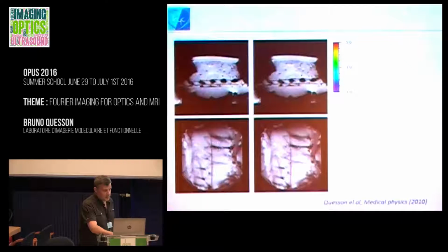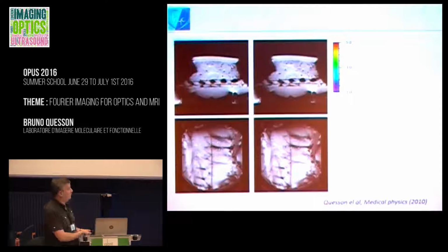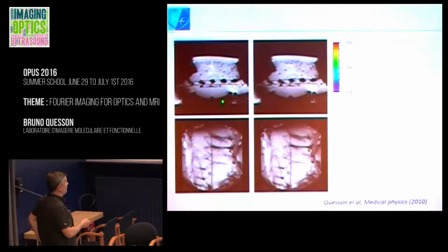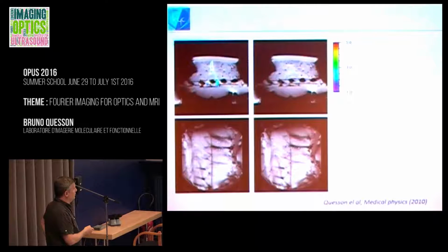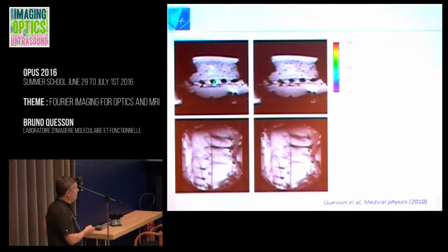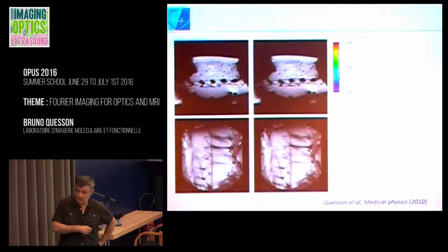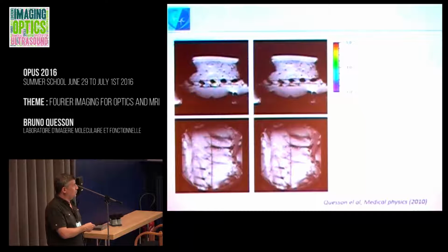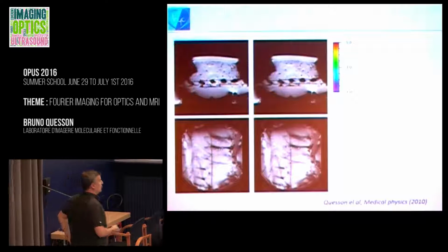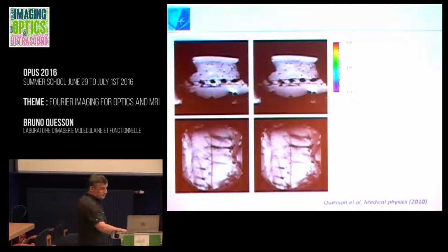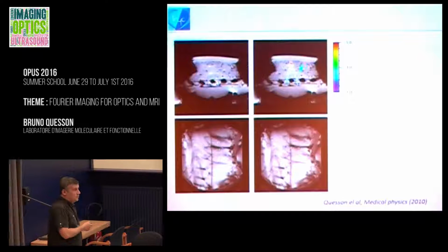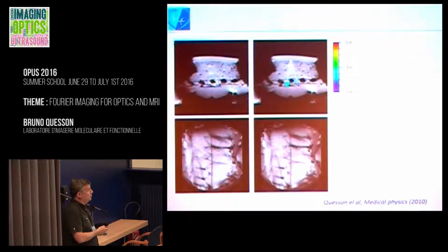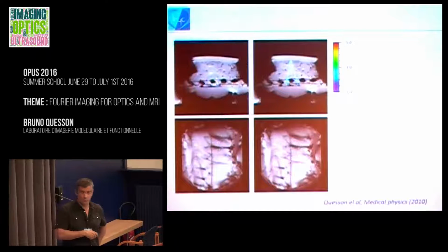Does this work? So you have an experiment there on the left. If you pay no attention, you use all the elements to emit. You're able to increase temperature there at the focal point, but then also around the bones, which is unwanted. And when you stop, it's decreasing there, but then since the bone is heating very efficiently, it's going to continue to stay warm, and you have accumulated energy. If you take care and switch off the elements that are in the shadow, you still get your temperature increase there, but you do not have any more temperature increase around your bones.